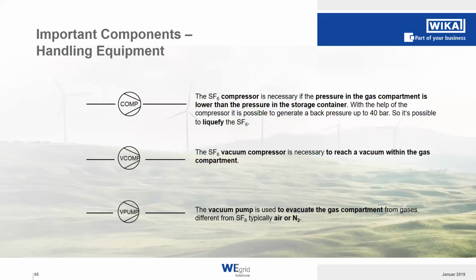In addition to our SF6 compressor, we have the SF6 vacuum compressor, and this is because the SF6 compressor can only go as low as the atmospheric pressure, and to reach that final vacuum for the evacuation of 1 millibar, the SF6 vacuum compressor is doing the rest of the work. And then we have the vacuum pump, which is responsible for evacuating or filling air or nitrogen into your compartment so that you are safe to go inside and do your maintenance jobs.